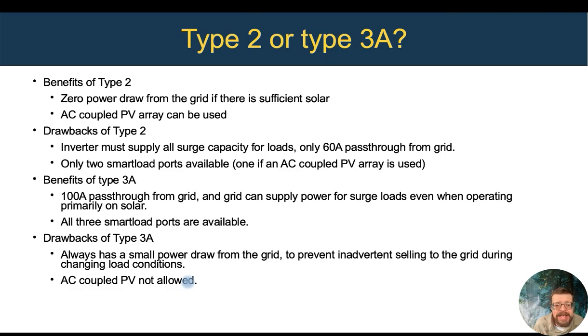So the benefit of a Type 2 is that it has zero power draw from the grid if there is enough solar. Because it's switching back and forth between the grid, it never has any power draw when it's powering the loads from solar. With a Type 3A, and all the Type 3 systems, because they're operating in parallel with the grid, in order to make sure that it doesn't inadvertently sell to the grid at any point when loads change and solar input changes, it always has to have this background draw from the grid, such that when the power draw bounces up and down, it doesn't go below zero draw from the grid and sell to the grid. So a Type 3A is always going to have this small power draw from the grid, usually 100 to 200 watts, to prevent that inadvertent sell back. So with a Type 2, it's zero power draw from the grid if you've got enough solar.